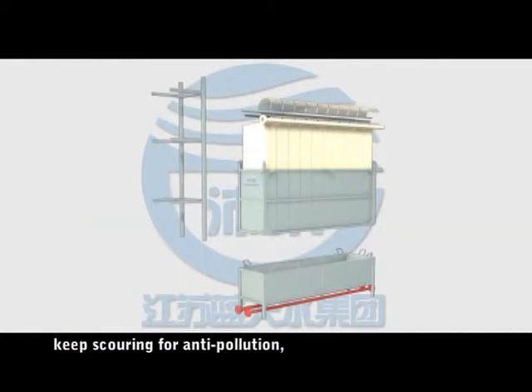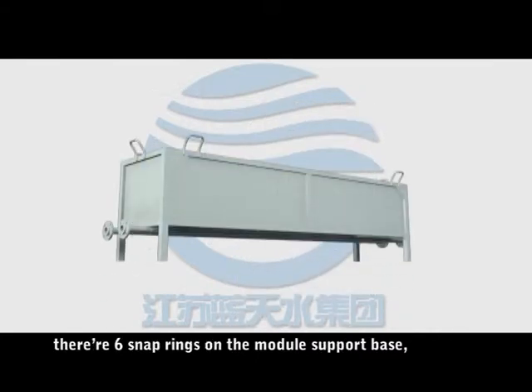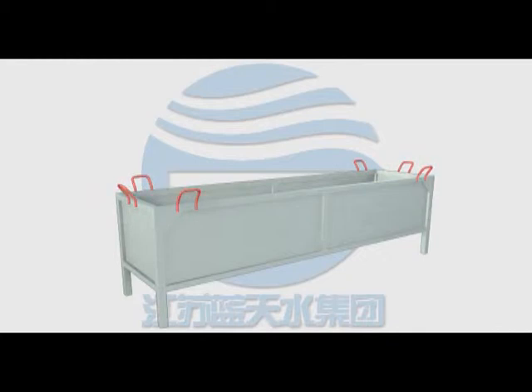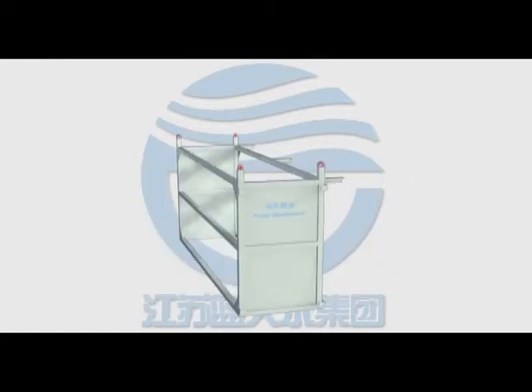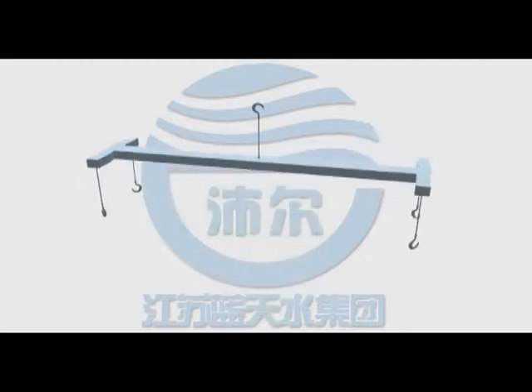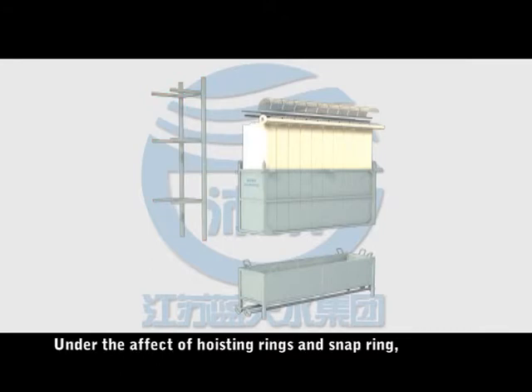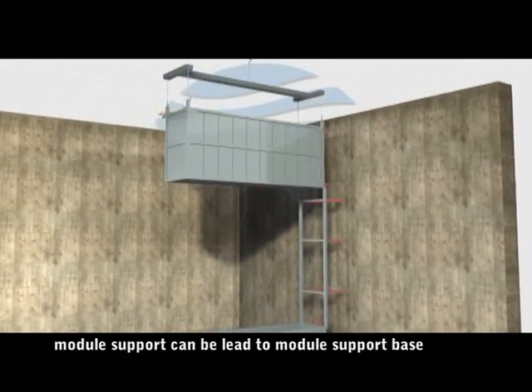The aeration pipe keeps scouring for anti-pollution and provides oxygen for the microorganisms in the MBR tank. The aeration pipe is fixed in the module support base, which has six snap rings for easy and correct installation. The guide rod is used to lead the membrane module. Under the effect of hoisting rings and snap rings, the module support can be guided to the module support base correctly.